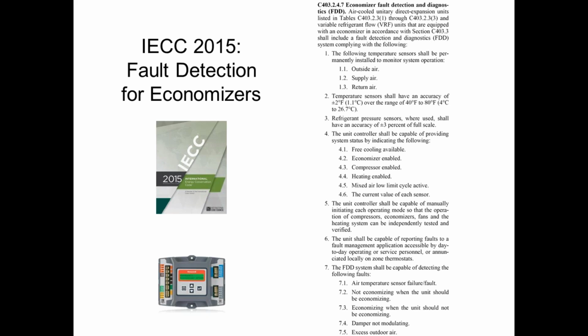There are multiple economizer controllers that can do that on the market, but you do need to ask for those things. If you just tell your supplier, give me an economizer, you'll get whatever they felt like giving you. Tell them I need an economizer with fault detection and diagnostics, or tell them you need a Honeywell Jade economizer or a Belimo Zip economizer or something like that by name, and then you're more likely to get what you want. So most of these things are built in. The economizer controller guys know how to do this. They have products that are quote-unquote stamped FDD. There's no rating system, but they're marketing in their literature as FDD, and it should be easy to find them.